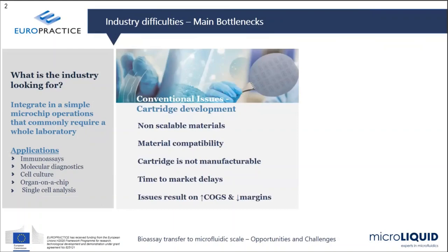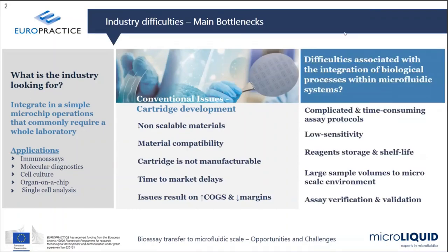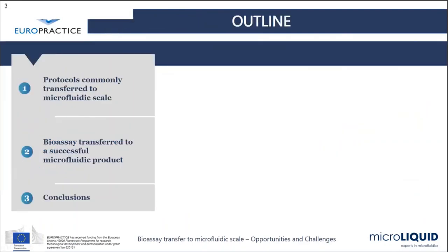There are conventional issues which have already been addressed for cartridge development, such as the use, until now, of non-scalable materials, how to get a material which is completely compatible with the bioassay, with the protocol that we need to run in the cartridge, and how to manufacture that in a mass production way. But there are indeed difficulties which are not related to the microfluidics itself, but to the bioassay. So when we are facing the integration of a bioassay protocol within a microfluidic device, we also need to reduce the complication of the bioassay, to reduce the time, to increase the sensitivity, and to solve problems related with reagents storage and shelf life of those reagents. So this is what I'm going to address during the course of this talk.